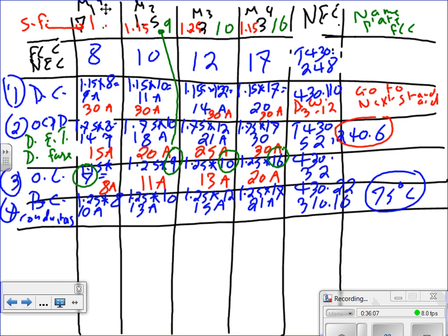Okay. Now you're going to go to which... If you say 21 amp cable, people start laughing at you. What are you talking about? I need wire gauge. How do you convert 21 amps into wire gauge? I hope you know by now to go to 310.16. So for 21, number 10, 14. These are motors. You're going to go to 75. Let's start with number 10. You can't use number 10 for number 12, number 14 anyway. So for number 10 would be what? 14. For 13 amps, that also will be 14. For this one will also be 14.